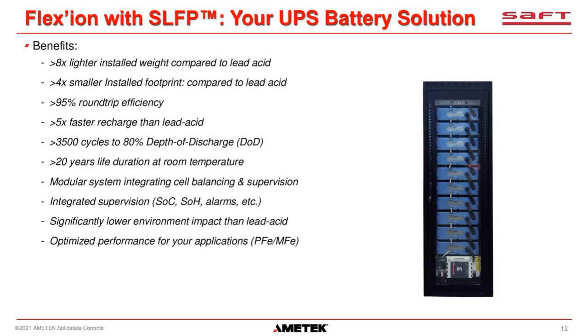So some of the benefits that SAFT lists for this Flexion lithium-ion battery is that it is greater than 8 times lighter than the installed weight of the lead-acid batteries, and it has a 4 times smaller footprint. The battery is more efficient than lead-acid and NiCad with 95% round-trip efficiency. You could charge the LFP lithium-ion batteries much faster than lead-acid or NiCad, up to 5 times faster, depending on the load on your UPS.